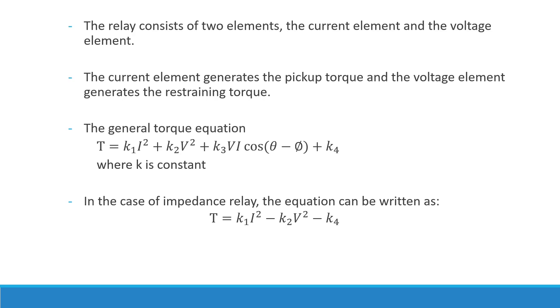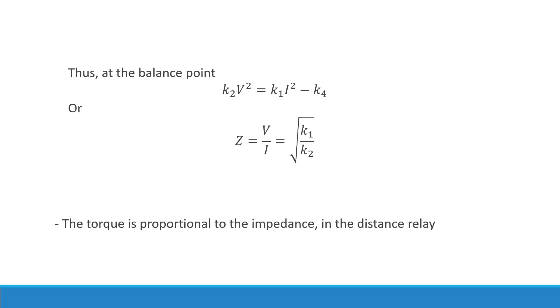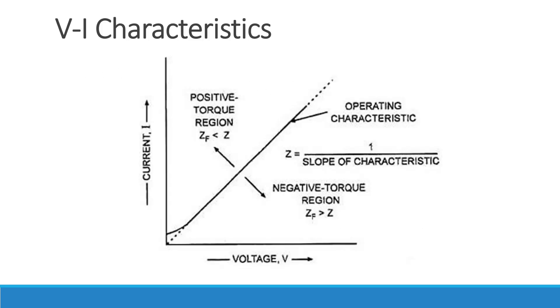The negative sign is because of the opposite direction of the voltage element. At the balance point we get K2·V² = K1·I² − K4, or V/I = √(K1/K2). From this we can understand that the torque generated in a distance relay is proportional to the impedance.